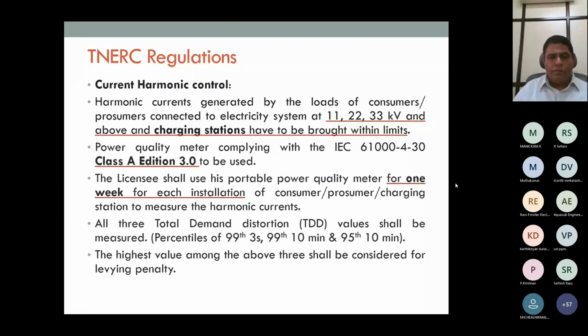So which meter do they have to use for measurement? It is an Edition 3 Class A IEC 61000-4-30 meter that has to be used. The electricity board right now was using a different meter which does not comply with current regulations, so they have to change. They were using one particular brand and one particular model. That old meter cannot be used. They have to purchase a new meter, and they have to come for measurement.